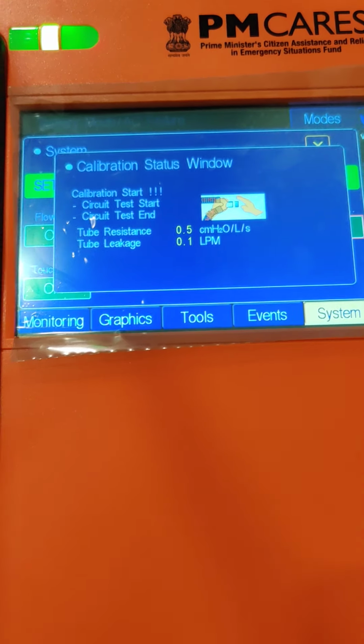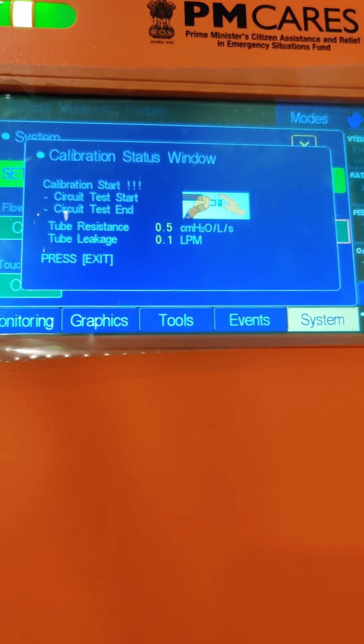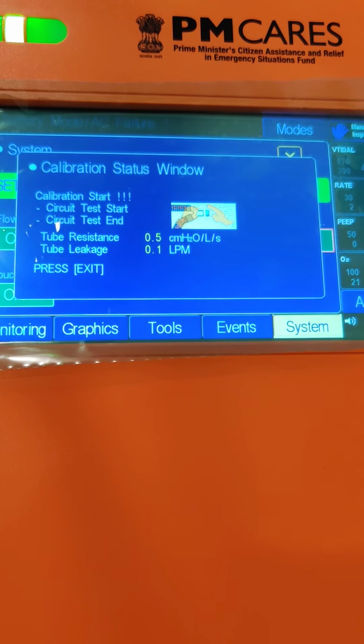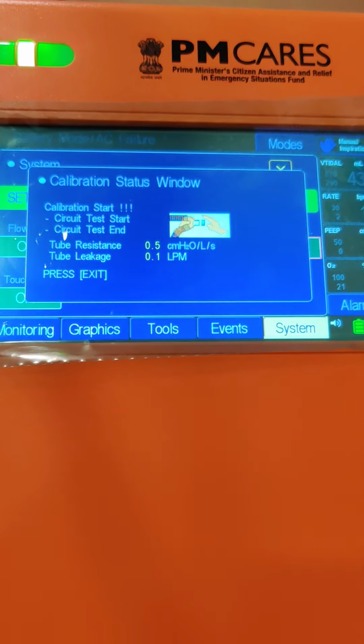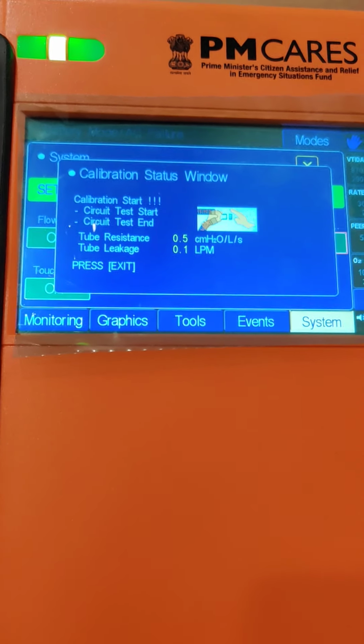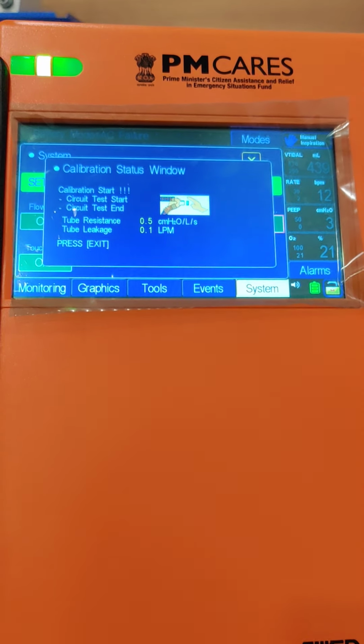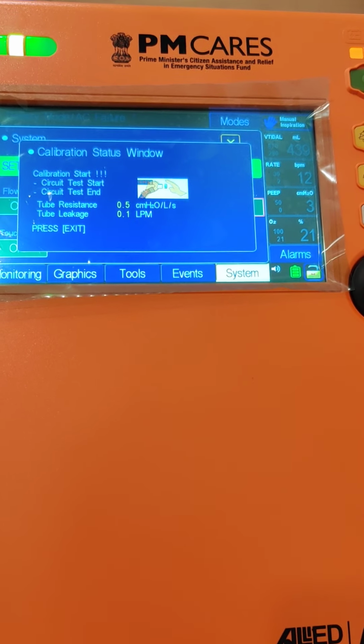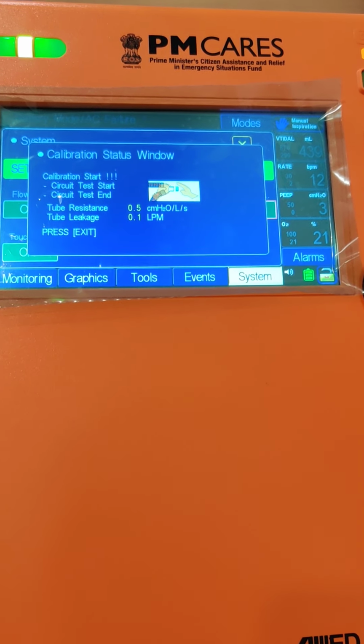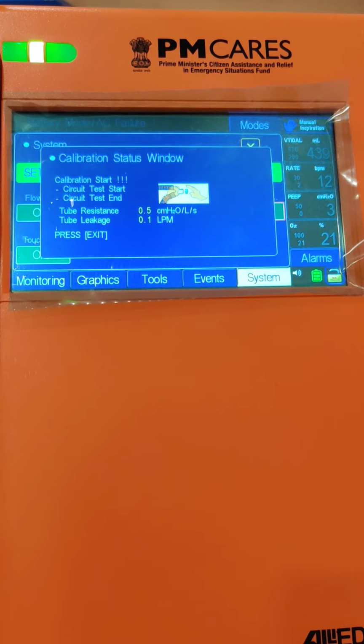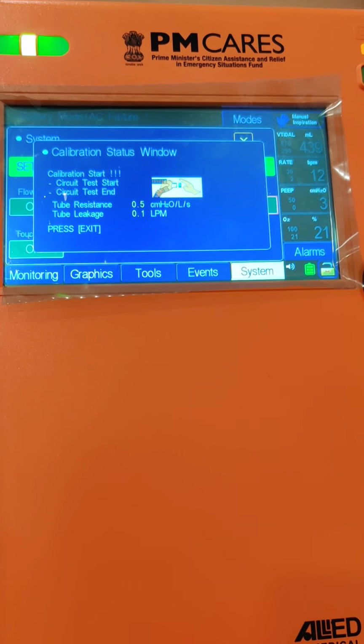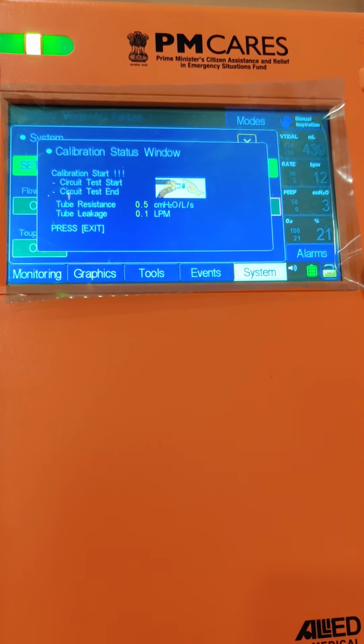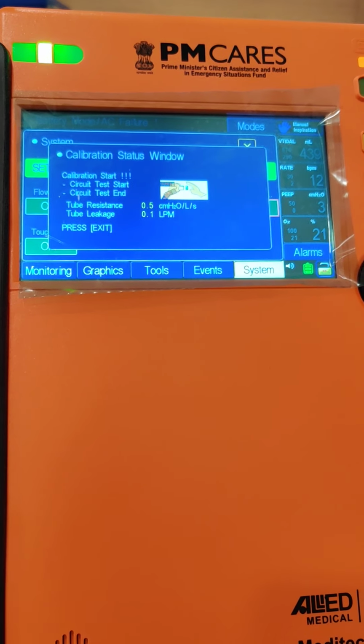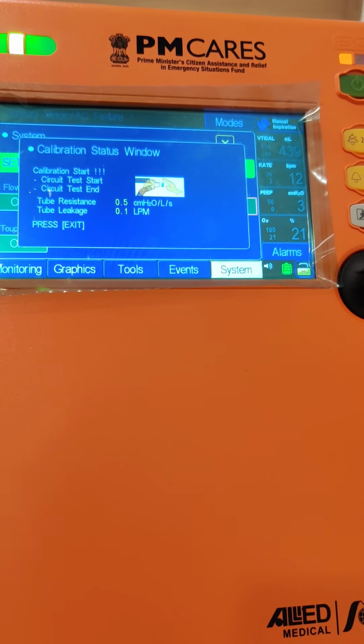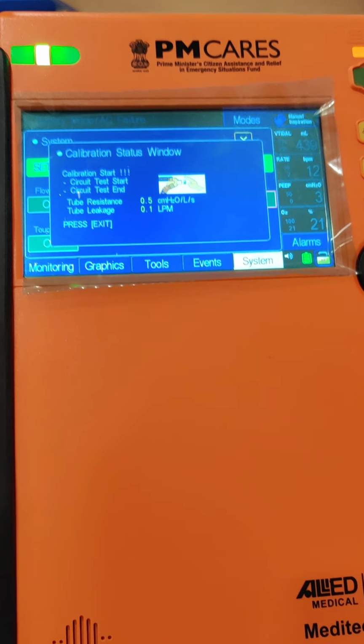It is showing a leakage of 0.1 liters per minute, and the tube resistance is 0.5 centimeters per liter per second. So 0.1 liters per minute is acceptable, and the ventilator will compensate for this leakage and deliver that much more tidal volume to the patient to achieve the settable tidal volume. So this is the only calibration that has to be done by the staff or the technicians at the start of the ventilation. Otherwise, the rest of the calibration will be done by the service engineers.